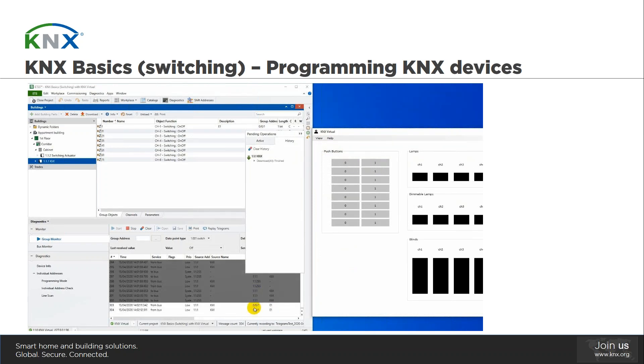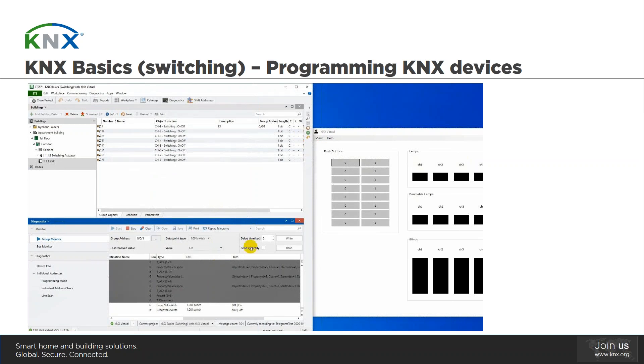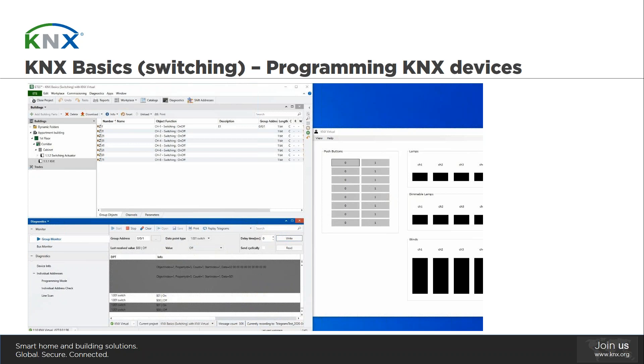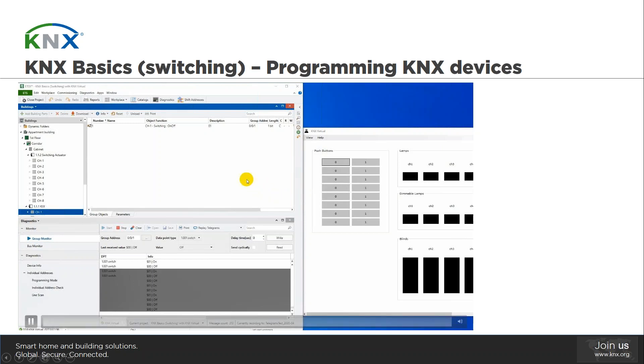We can also see the telegrams running in the monitor during the download. After the download is completed, we are able to switch ON and OFF the lamp via the Base view rockers from the push button. Furthermore, we can see the telegrams exchanged when operating the lamp via the push button directly in the monitor. The telegrams are sent by the device with individual address 1.1.1, which is the push button. And if we trigger the OFF value from the monitor, the telegram comes from individual address 1.1.255, which is the address of the interface.